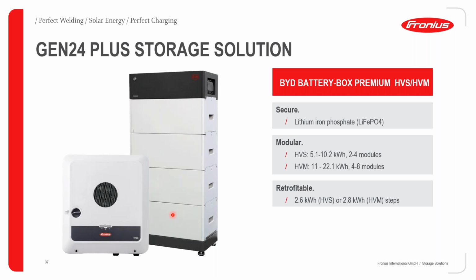So it's also, like I said before, retrofittable. You can start with the number of stacks or modules allowable by your budget at the beginning. And then later on, the BYD battery box is quite flexible, and you're able to add either modules or attach battery stacks to operate in parallel, at a maximum of 3, as my colleague had earlier mentioned. There's also a lot of ease in terms of installation, because the entire battery stack is ground mounted, and therefore you don't need to struggle with positioning it on a wall mount system. This also provides for very easy commissioning through a very nice wizard that is provided by BYD.